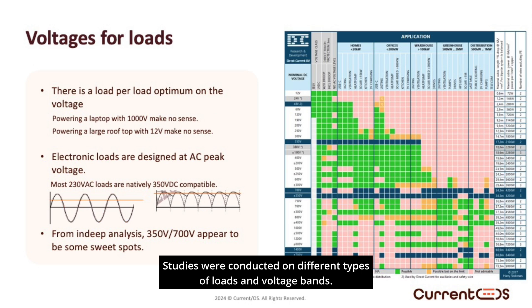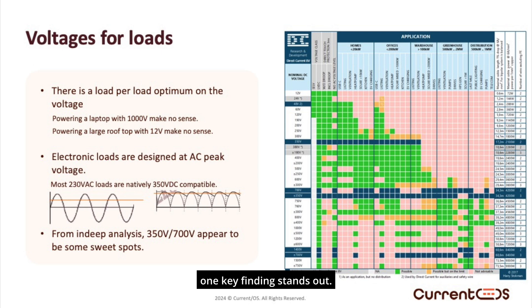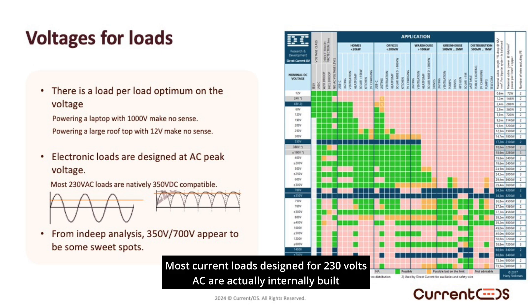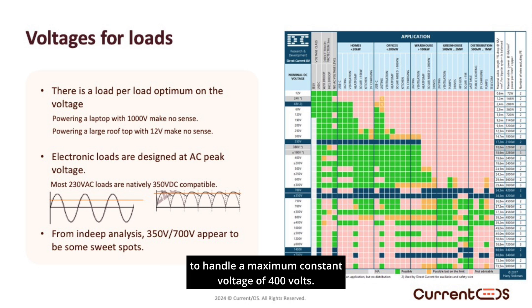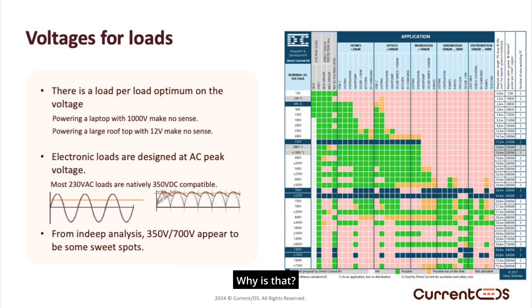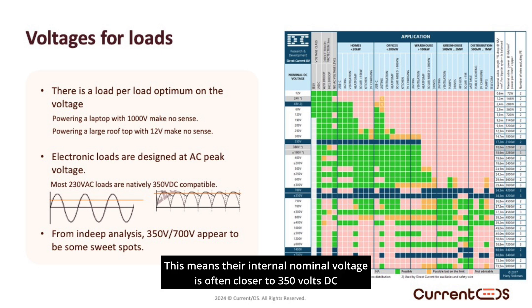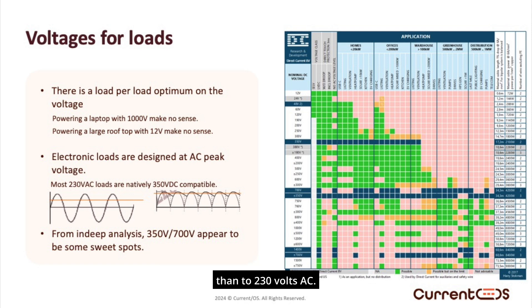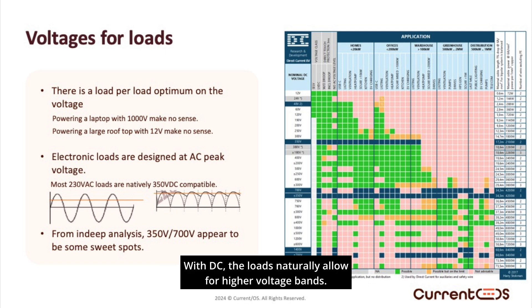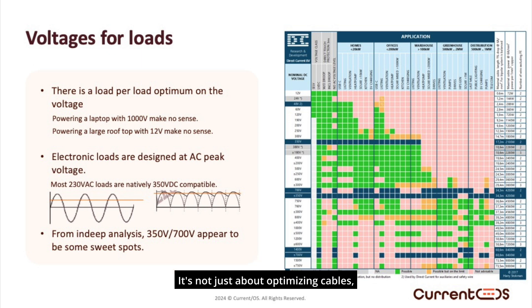Studies were conducted on different types of loads and voltage bands, and one key finding stands out. Most current loads designed for 230 volts AC are actually internally built to handle a maximum constant voltage of 400 volts. As a result, they perform very well around 350 volts DC. Many of today's AC loads include internal electronics, and the first thing those electronics do is convert AC to DC. This means their internal nominal voltage is often closer to 350 volts DC than to 230 volts AC. With DC, the loads naturally allow for higher voltage bands — it's not just about optimizing cables, it's the way many existing products are designed.